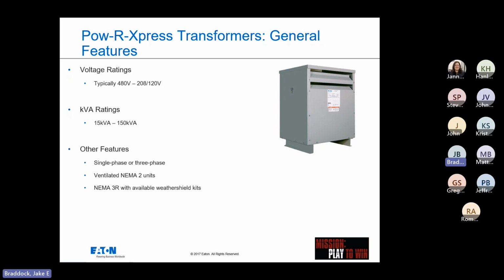So again, typical voltage range is 480 to 208, 120, step up or step down, with a kVA rating of 15 to 150, all on Schaedler shelves. Some other features, we can have single or 3-phase. Now these units are similar to the photo you see here, a ventilated transformer, which is standard NEMA 2. We can make them NEMA 3 with some weather shield kits, which are also easily accessible.